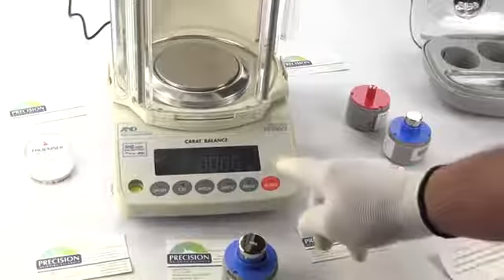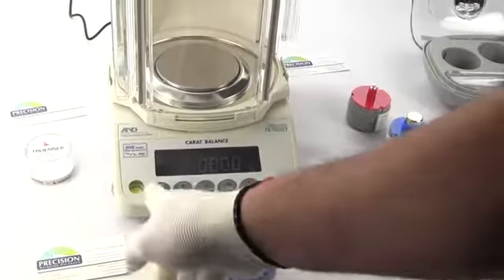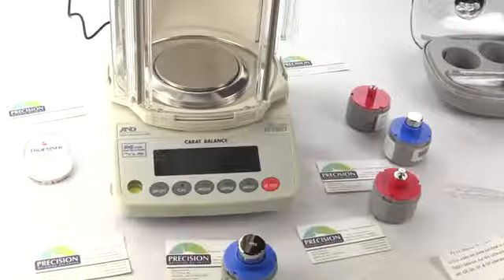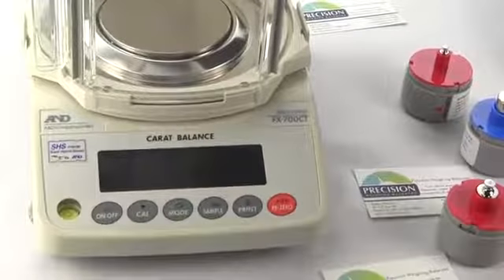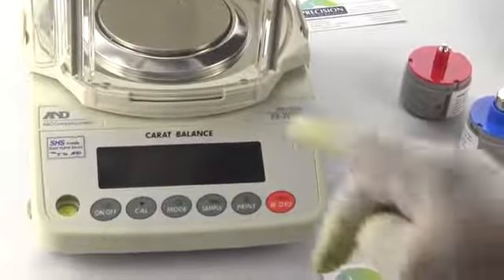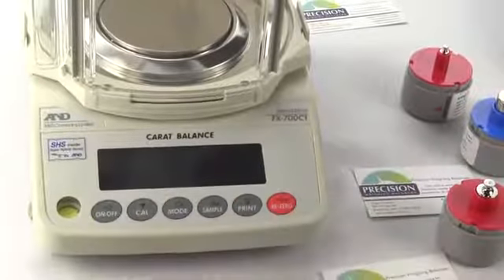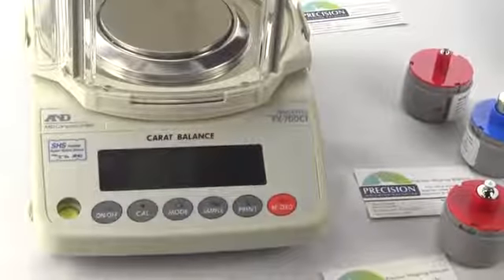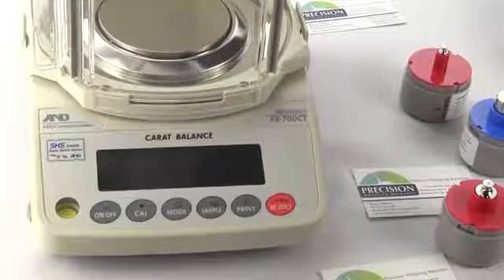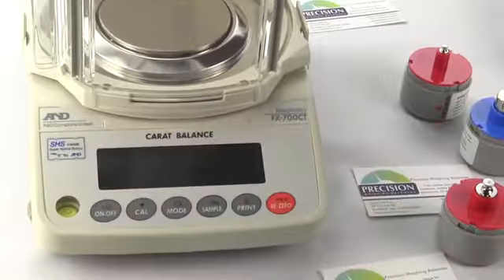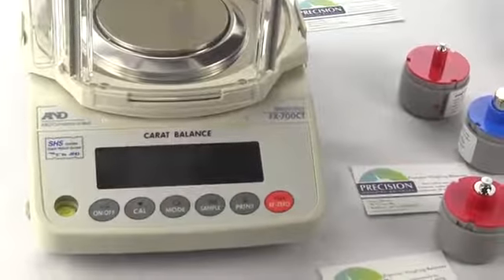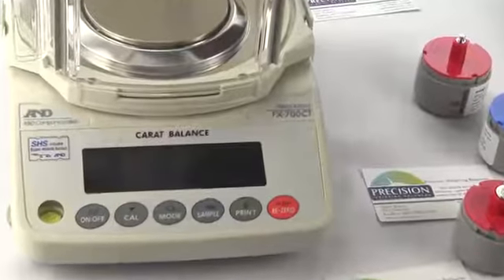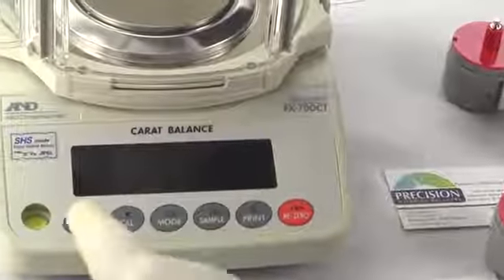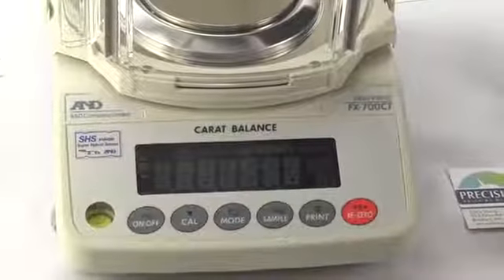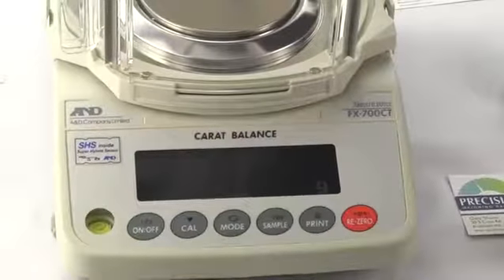So right now we have the display on. If we were to turn off the balance, you'll notice in the lower left-hand corner there's an arrow. That means that this balance is in standby mode. It's kind of hard to see, but it's in the very lower left-hand corner. And that just means that power is going to the balance. So you don't have to have the display on, but you have to have the balance plugged in for at least 1 hour before doing calibration. And then when the balance powers up, it should go to 0.